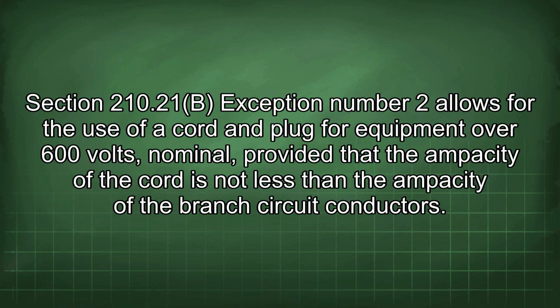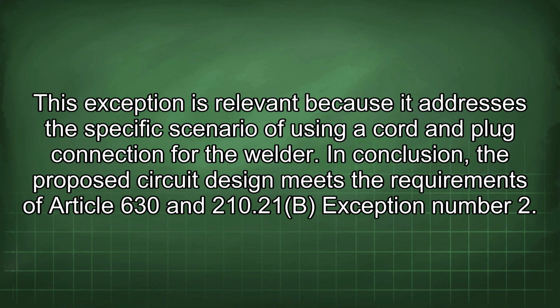Section 210.21(B) exception number 2 allows for the use of a cord and plug for equipment over 600 volts, nominal, provided that the ampacity of the cord is not less than the ampacity of the branch circuit conductors. This exception is relevant because it addresses the specific scenario of using a cord and plug connection for the welder.